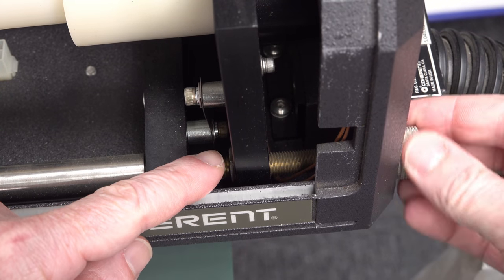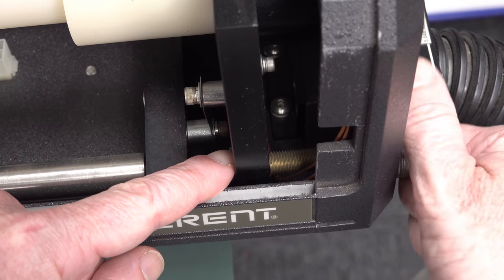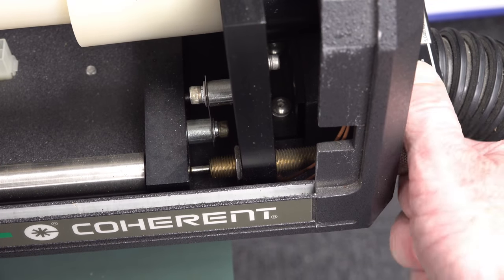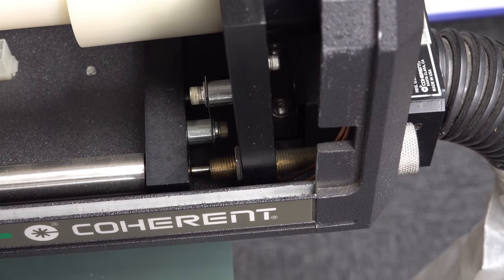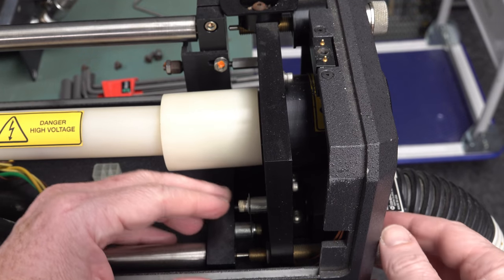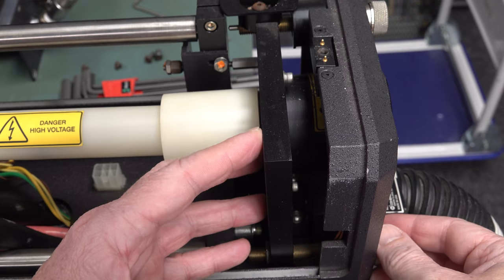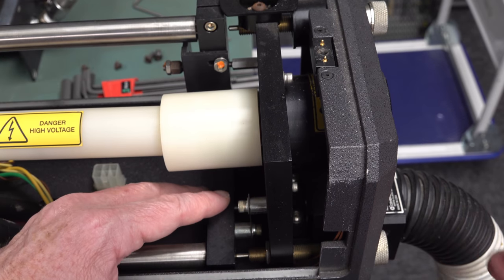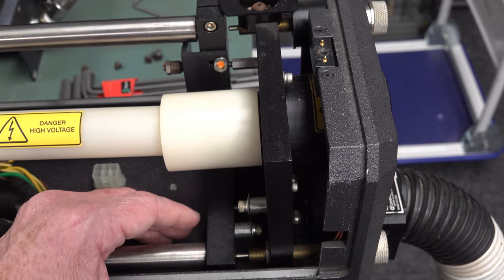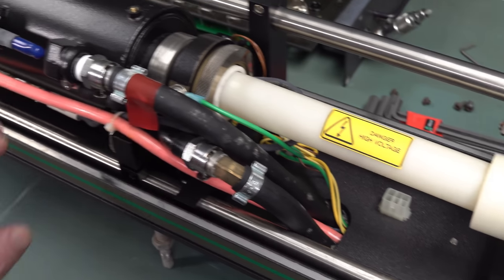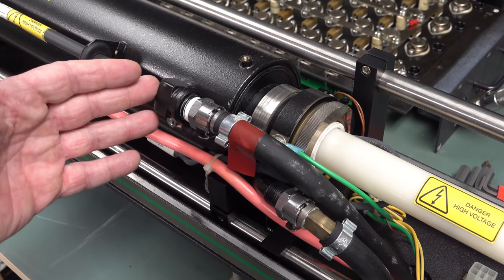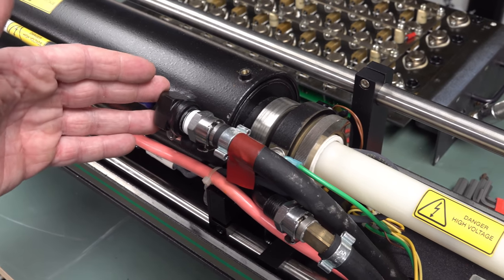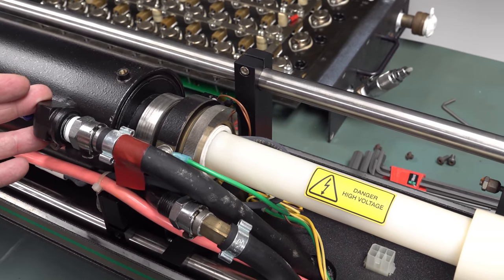So because you have to align all of the precision mirrors in these and everything else. And that's what these knobs here do. And you'll see that this here just changes the angle of this very, very slightly. And it doesn't take much for you to change the output power of this thing based on the angles of the mirrors. And for those technically minded, just 10 micro radians of angle out on the mirror that's part of the resonant cavity in here is enough to measurably change the output power of this thing. So yeah, it's critically important.